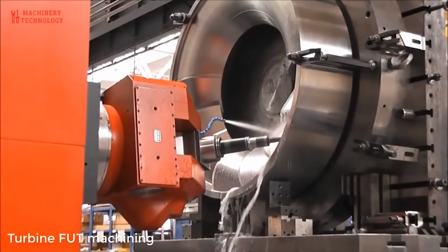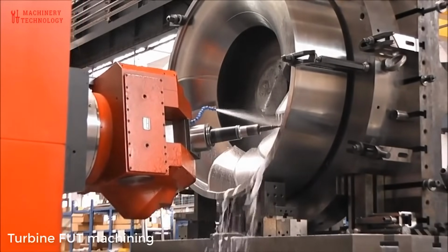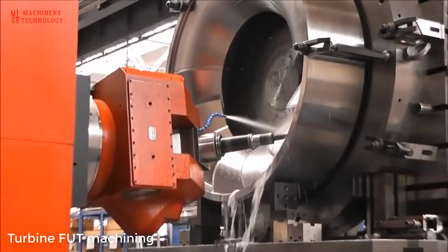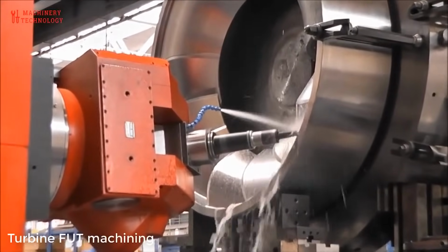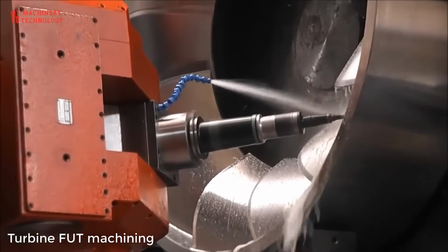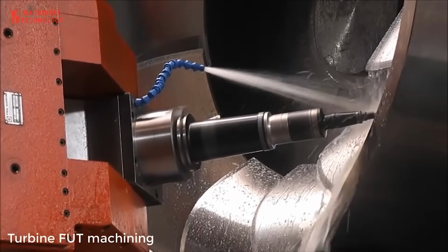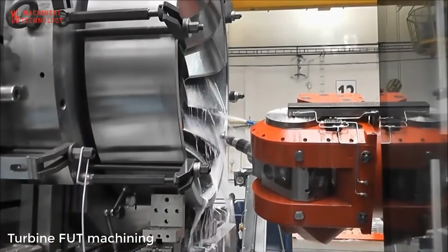Reaction turbines. In a reaction turbine, forces driving the rotor are achieved by the reaction of an accelerating water flow in the runner while the pressure drops. The reaction principle can be observed in a rotary lawn sprinkler, where the emerging jet drives the rotor in the opposite direction. Due to the great variety of possible runner designs, reaction turbines can be used over a much larger range of heads and flow rates than impulse turbines.